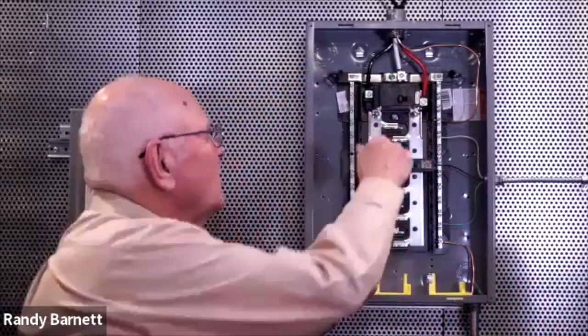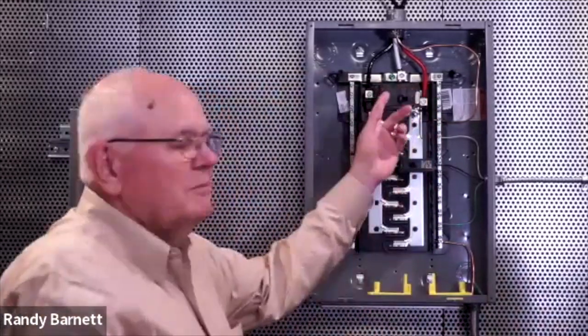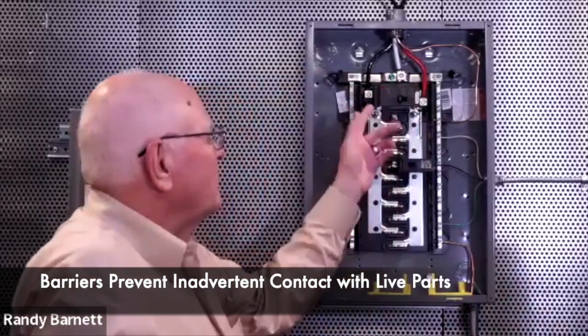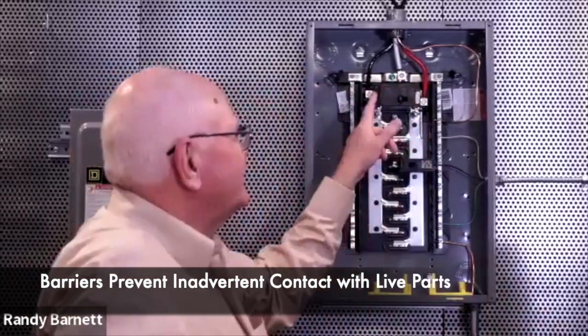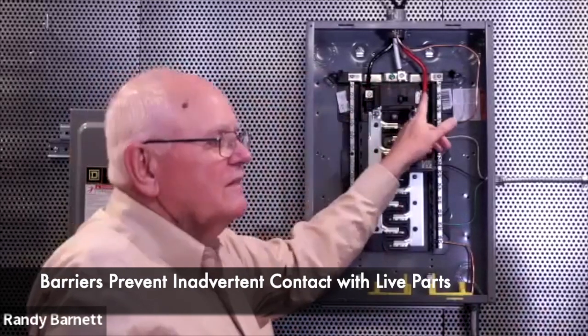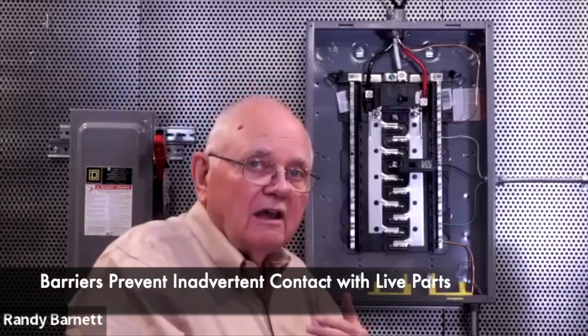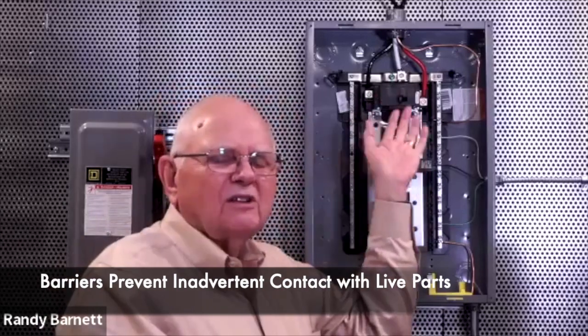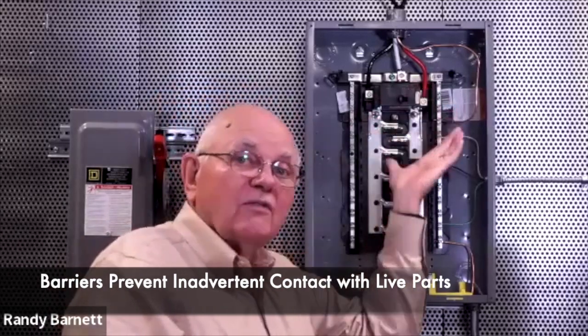So first of all, I have a barrier. A barrier is something that prevents me from inadvertently touching something I shouldn't. So for instance, in this panel board up above, even if I turn the main breaker to the off position, I still have an opportunity to inadvertently touch one of these line terminals coming in. And of course, those line terminals are going to be energized, aren't they? Because the main breaker turns off everything down below, but not the incoming power. So I could inadvertently touch those.